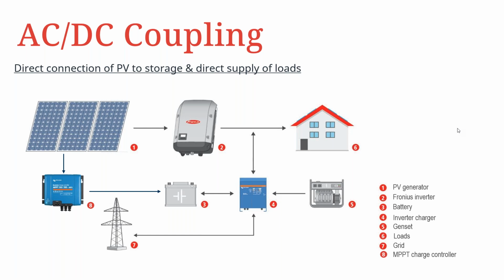To maximize the benefits of both configurations, DC and AC coupling, we highly recommend that you combine the two. Therefore, we have the direct connection of the PV to storage and direct supply of the load. In this case, a portion of your PV array is DC coupled to the battery system, and the biggest portion is connected to the PV inverter, which is then able to supply directly to the loads during the day.